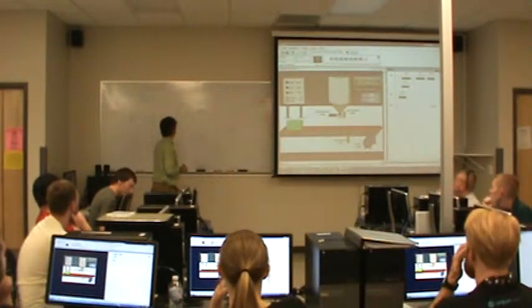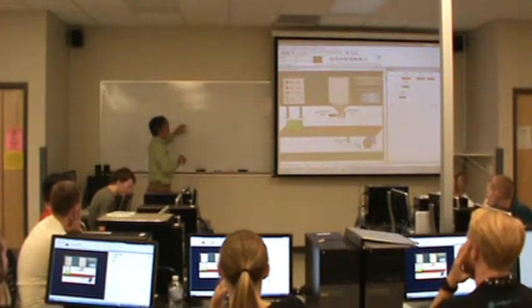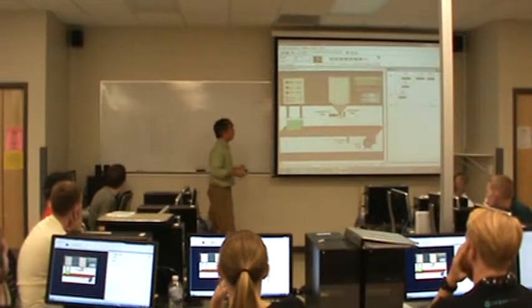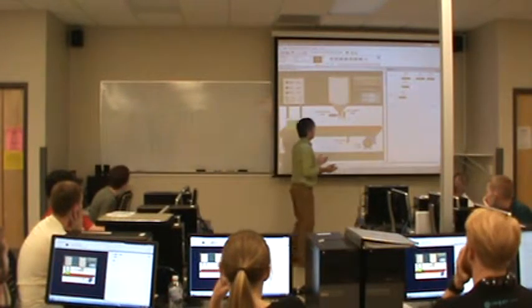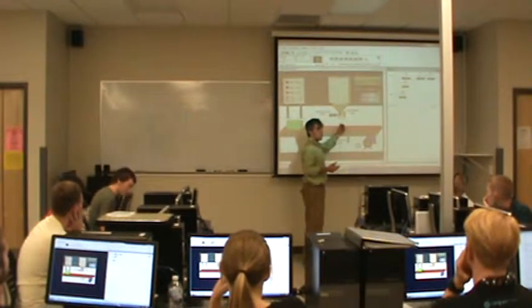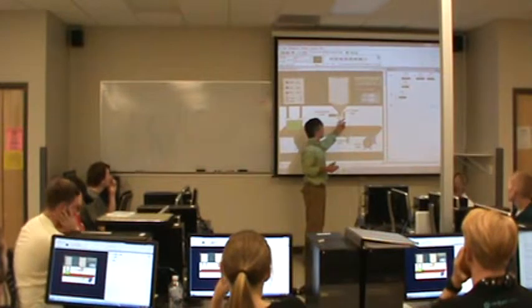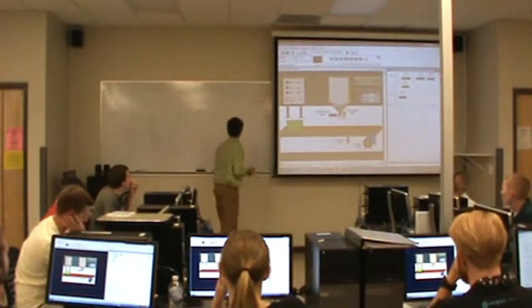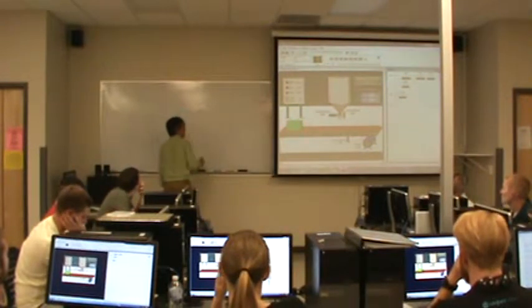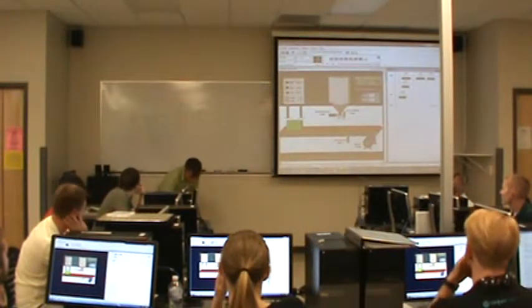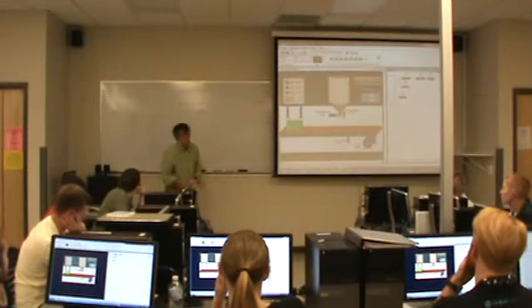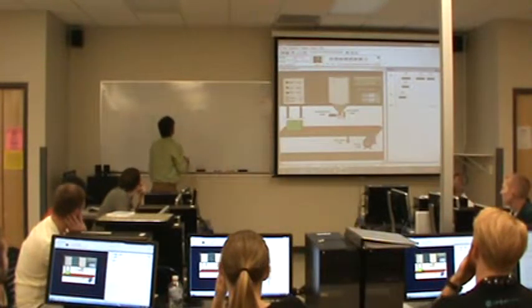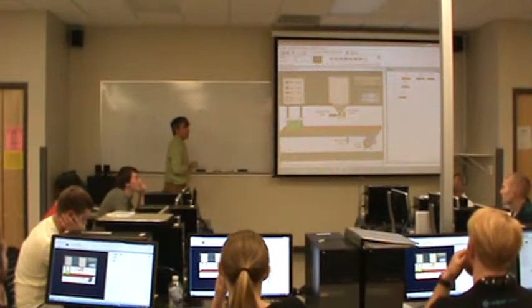If prox is off but level is true, what does that mean? Probably that we've got a problem, right? It means that this level sensor shouldn't be on, right? So in that case, we really don't care. Let's just say that motor is on at that time, because apparently something's wrong. We just need to keep the system running. Maybe everything will correct itself. That's a hope that doesn't ever pan out.